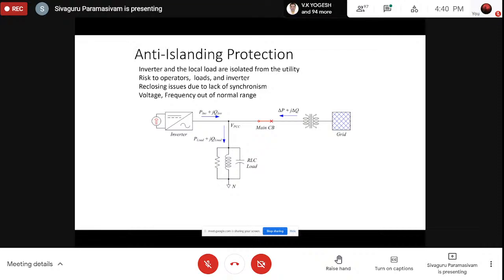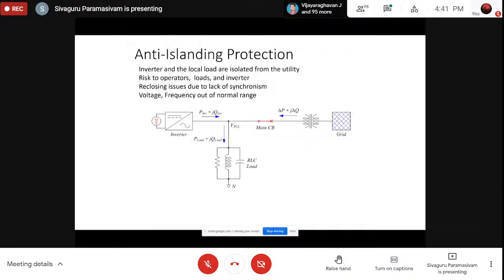Well, imagine that an inverter is having the capability to pump the power back to the grid when there is no grid. So our TNEB friends might have switched off the circuit breaker, and they will be doing something on the power network. And if the inverter connects back to the grid, what will happen? It's going to be a fatal accident, right? Because the power is going to flow, and whoever is going to work in the network is going to be electrocuted.